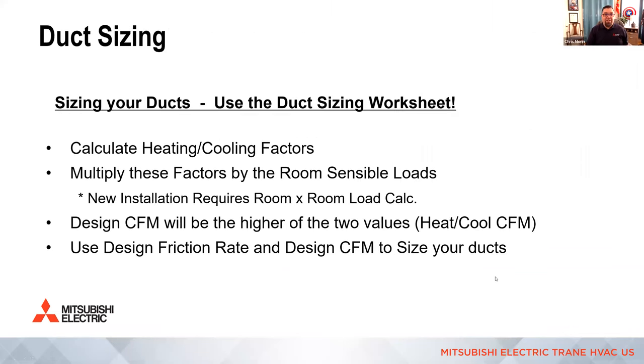All right. So we're going to size these duct runs using the worksheet. So I'm going to walk through this example first and then make sure everybody's clear on the process, because obviously we're just doing one or two rooms here. And then we're going to do a whole floor with a mid or high static air handler. So in order to do the worksheet on the back, the second page, right, we need to calculate our heating and cooling factors. I'm going to walk you through this example and how to do this. And then we're going to multiply these factors by the room sensible loads.